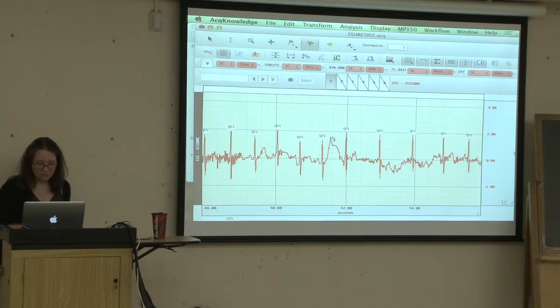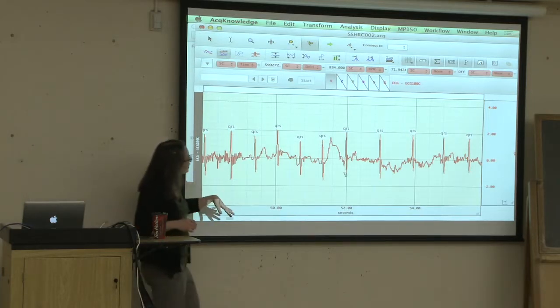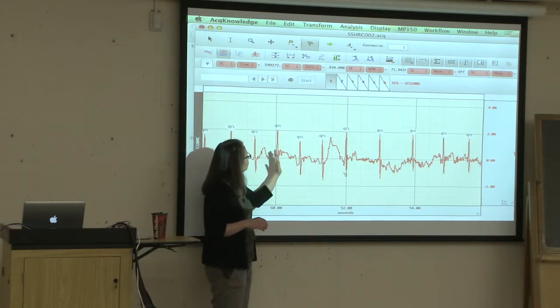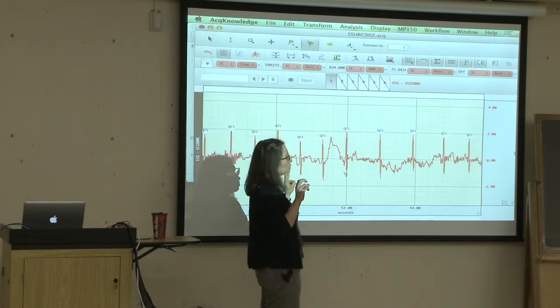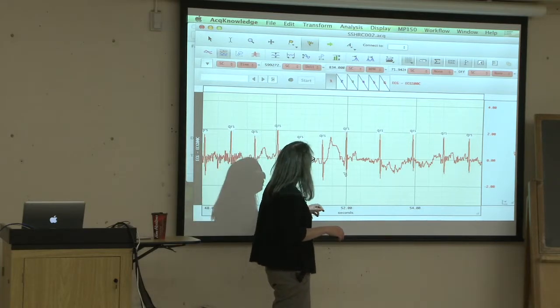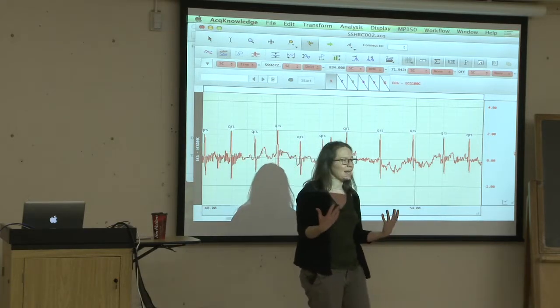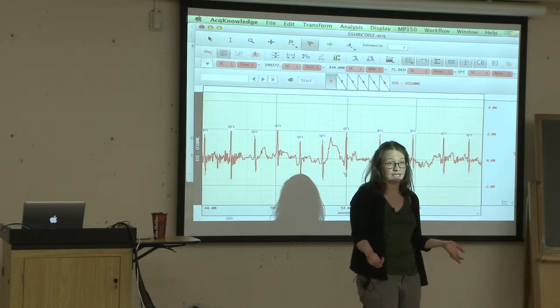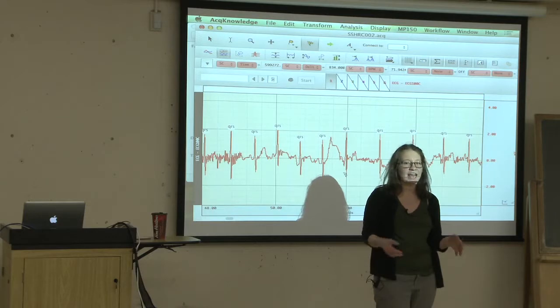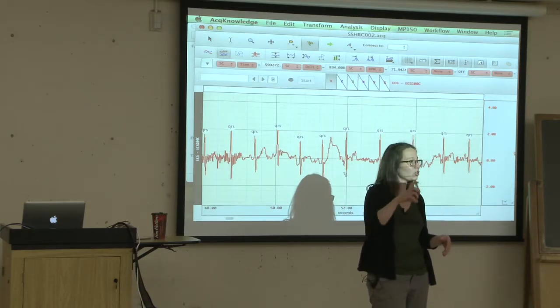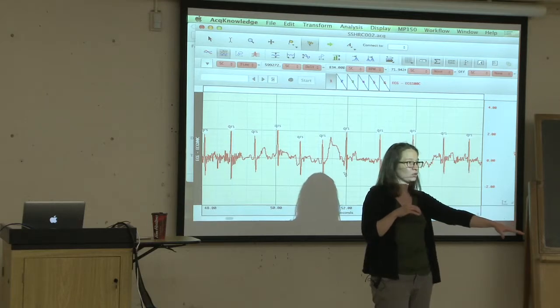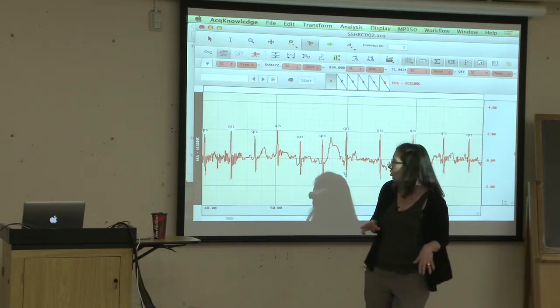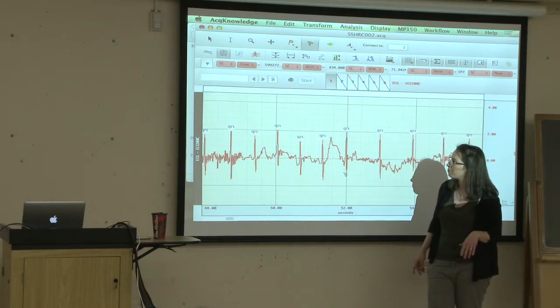Oh, there is something else I should say, I'm sorry. With each person, you'll notice, we call this individual stereotypy, every person has their own signature for their ECG wave, for example. Same with their impedance wave. And every time I hook up the same person, their ECG wave will look the same, even over the course of years, unless they have some kind of heart problem that occurs in the meanwhile.